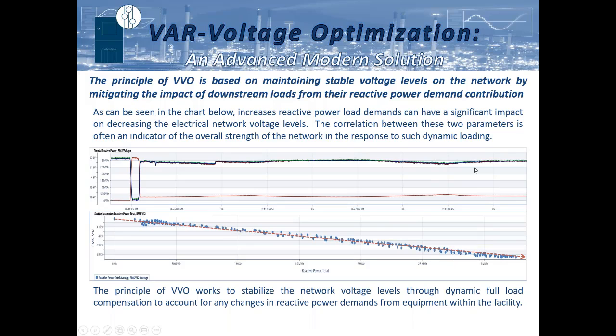So the ELSPEC works on a different principle. Although our systems are power factor correction solutions, that's really a side effect of the main purpose and functionality of the equalizer system. Our system works on the principle of VVO, which is VAR voltage optimization, and it is based on the correlation between the voltage level and the reactive power demands of all of the equipment downstream.